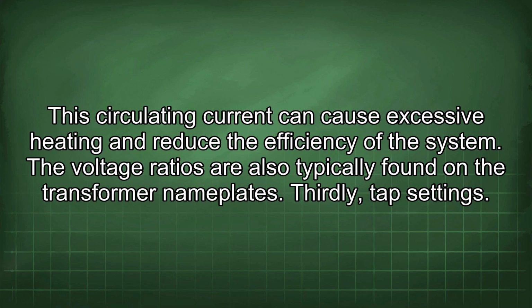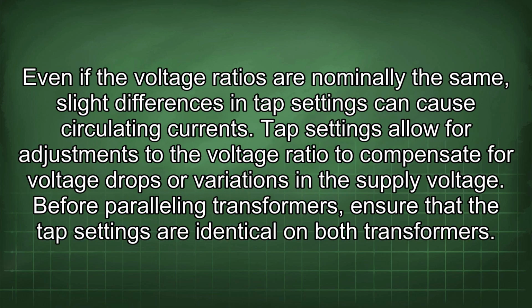Thirdly, tap settings. Even if the voltage ratios are nominally the same, slight differences in tap settings can cause circulating current. Tap settings allow for adjustments to the voltage ratio to compensate for voltage drops or variations in the supply voltage. Before paralleling transformers, ensure that the tap settings are identical on both transformers.